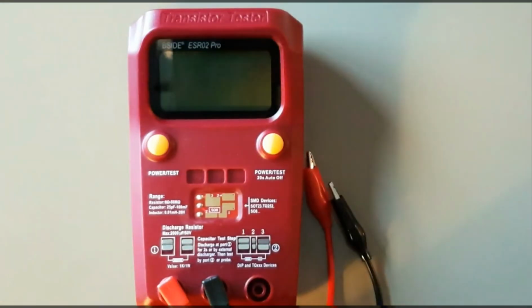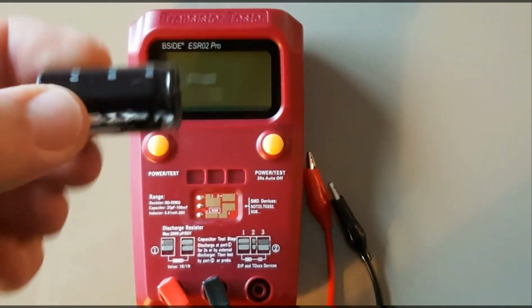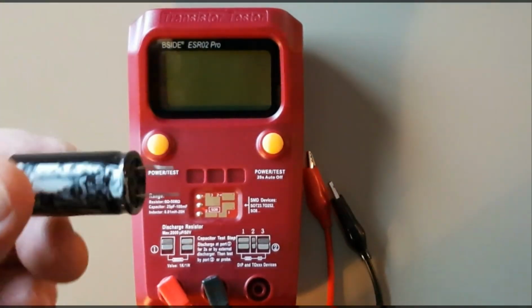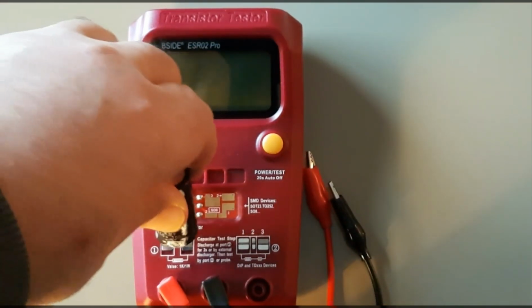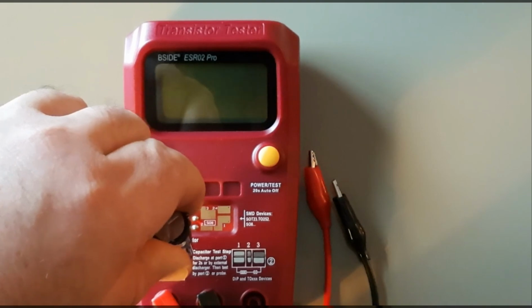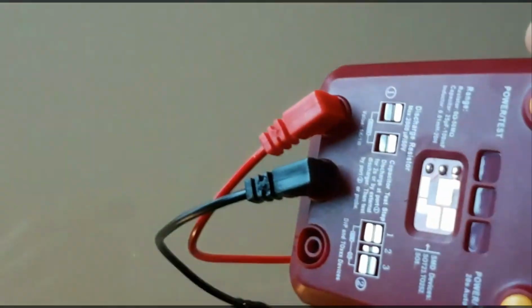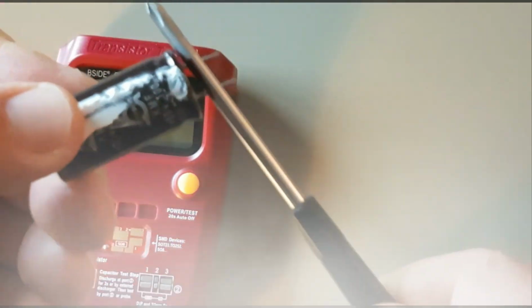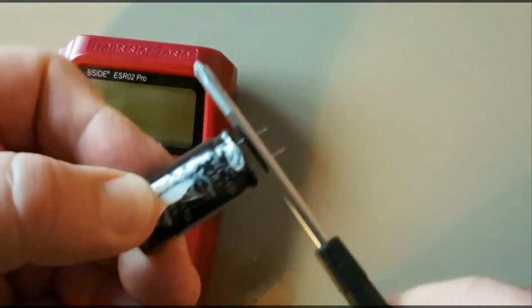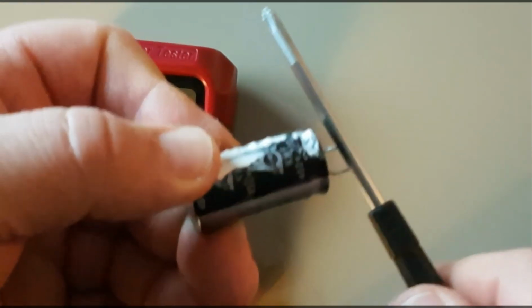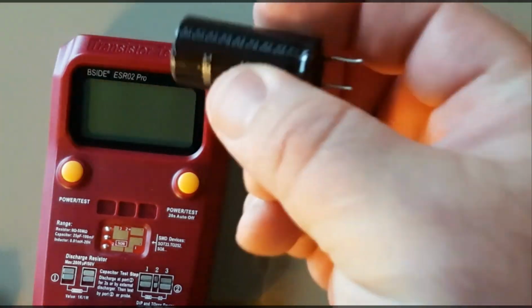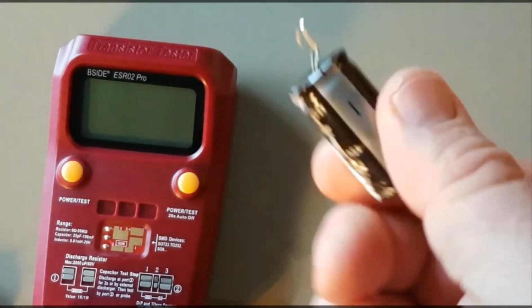Now, as I said, this particular device here, we could not use because it's rated at 50 volts. And if this was a fully discharged cap, which it is not, it's been discharged already, it would blow the meter. But if it was 50 volts or under, technically all you had to do is sit it on the discharge plate like so, wait 2 or 3 seconds, the built-in resistor inside will automatically discharge it. Of course, you can use the standard screwdriver method. Once again, if this had 400 volts in it, it could probably arc and it would glue the capacitor to my screwdriver and create a heck of a bang. So be very careful when you're dealing with high voltage caps. Please.